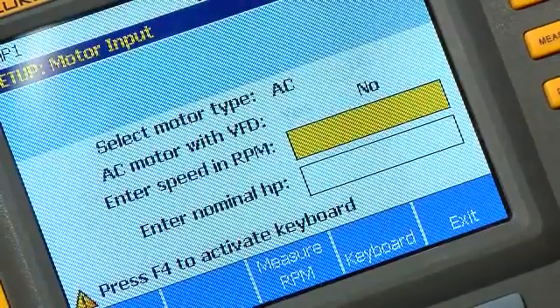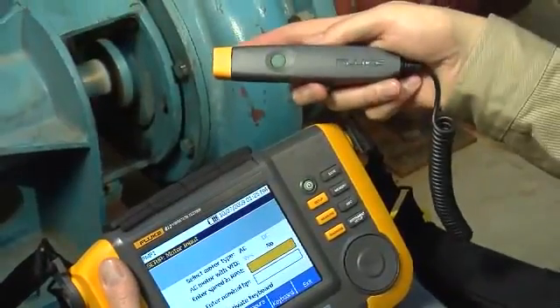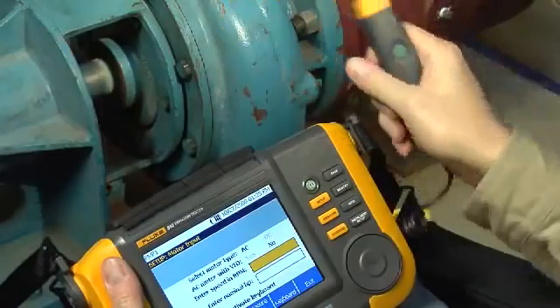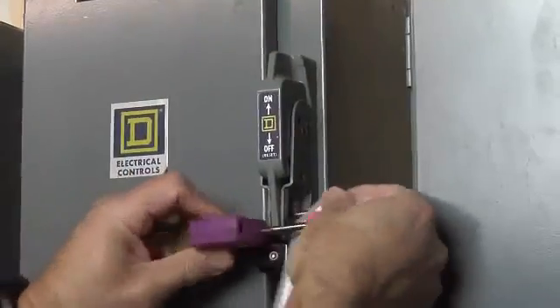Entering the correct running speed is critical to an accurate diagnosis. The Fluke 810 ships with an integrated laser tachometer for measuring the running speed of rotating equipment. Before using the laser tachometer, make sure to turn the motor off.